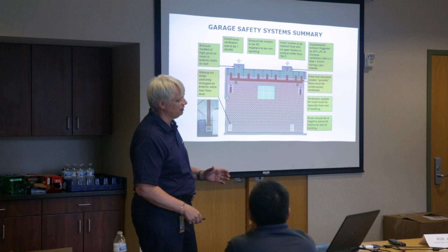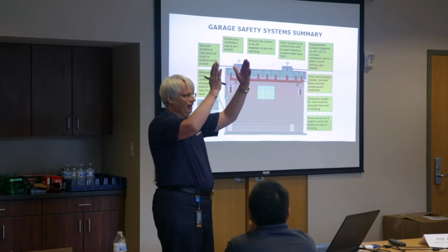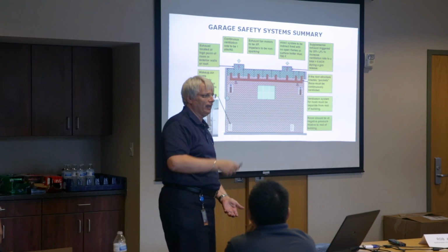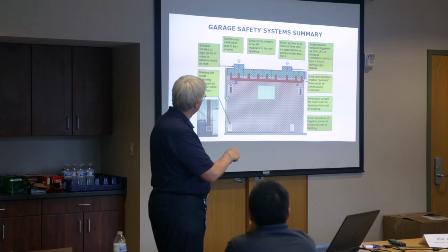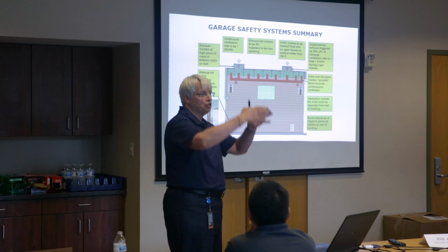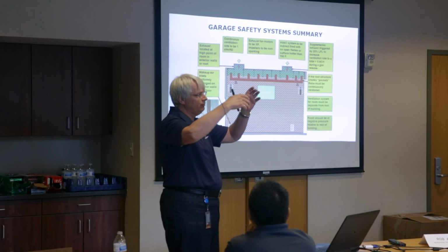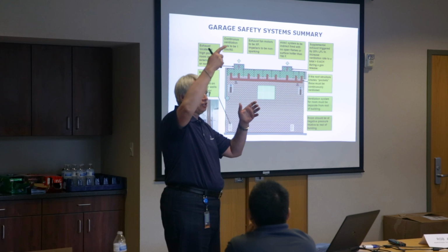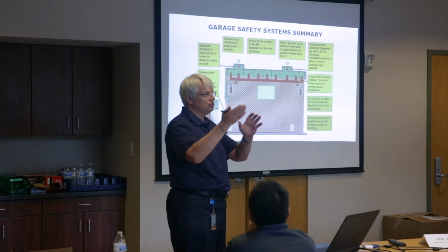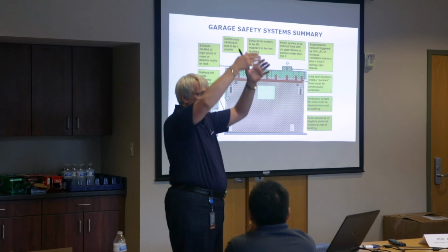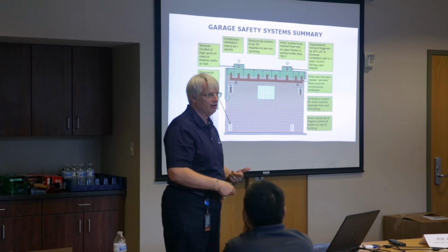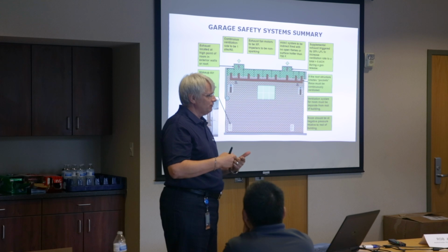If you have a facility that is 20 feet high, from the floor to the underside of your structure, in an hour, you'll move 60 times 1, so you'll move 60 cubic feet in an hour. If you look at that volume, if it's 20 feet high, 60 divided by 20, you've got 3 air changes in an hour. You're moving 60 CFM in an hour, and your volume per square foot is 20 cubic feet, so you're changing the air 3 times in an hour.